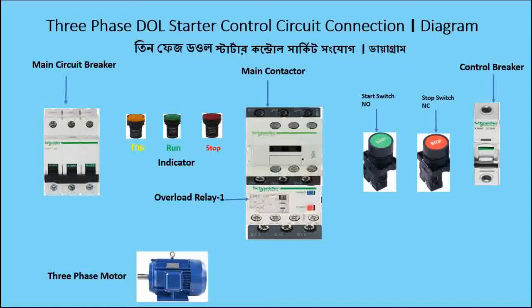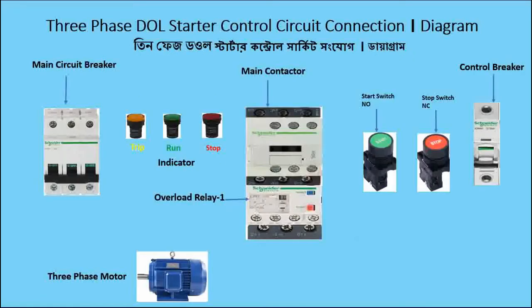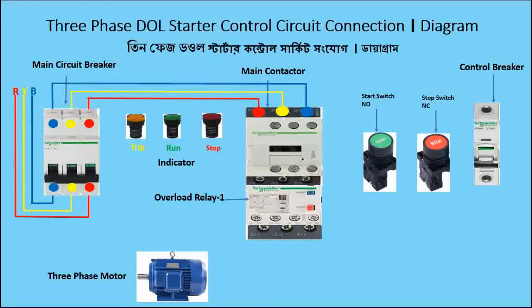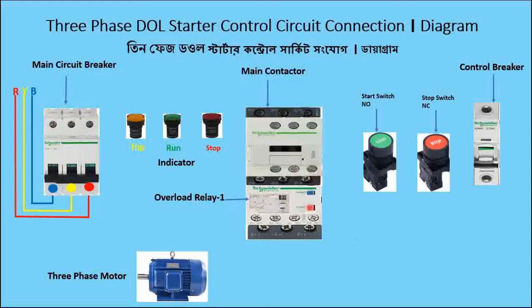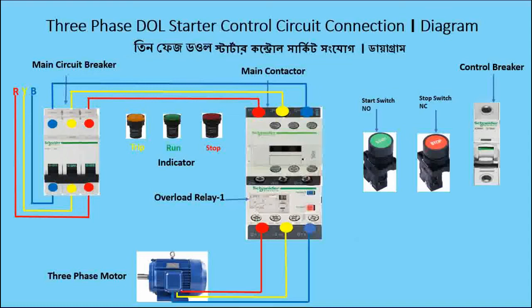This is the total wiring accessory for the three-phase DOL starter control circuit. Now I'm going for the connection. First I do the power cable connection: power cable from supply goes to main breaker input, then output goes to the main contactor — RYB — you can see there, input and output RYB through the main contactor, then through the overload relay, then to the motor as load.